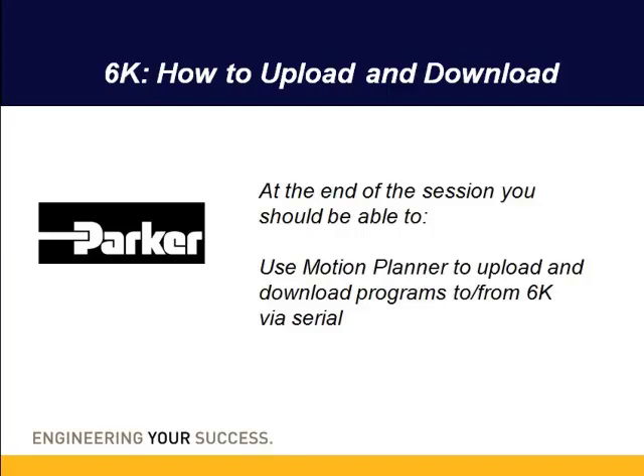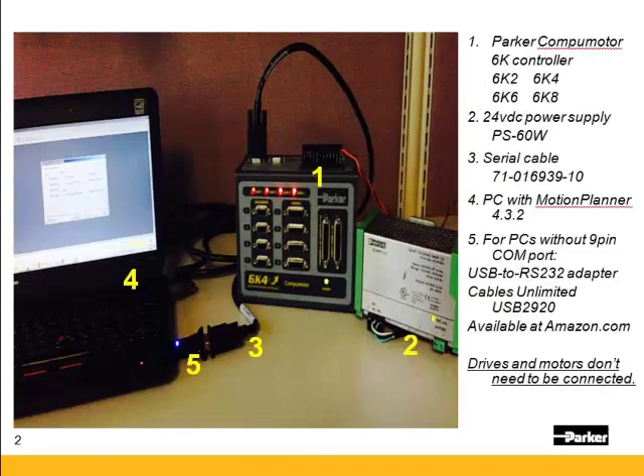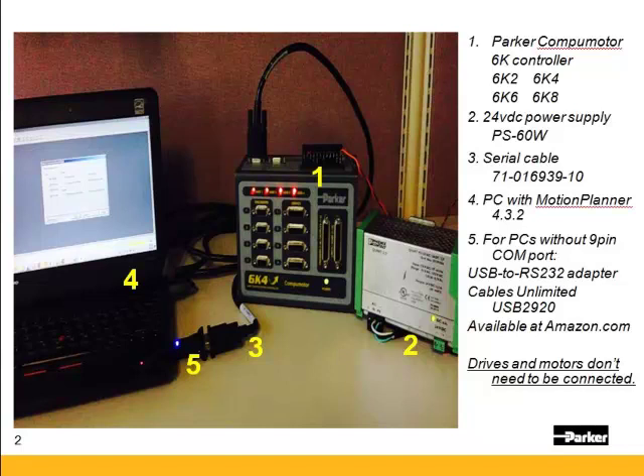I'll also show some of the basic commands to check the controller status. You'll need the controller powered on. The 6K requires 24 volts for control power for communication. We offer the PS60W power supply. You'll need a serial crossover cable which is a null modem. Our part number is 71-16939-10 and is a CE rated cable.